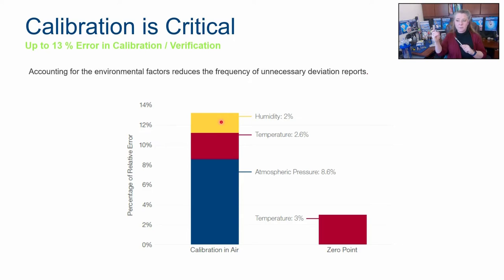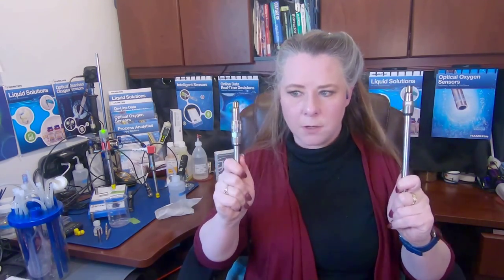Failing to have stable temperature when you're doing your measurements can introduce another 2.5 to 3% error. And failing to take into account humidity can add another 2% measuring error. It all adds up. We're going to talk about types of calibration first, and this is really important. This impacts polarographic versus optical differently.